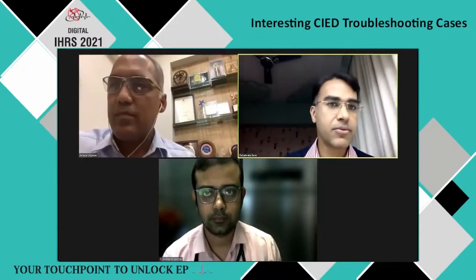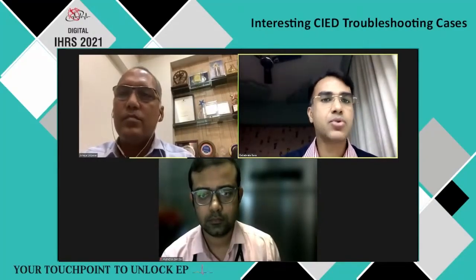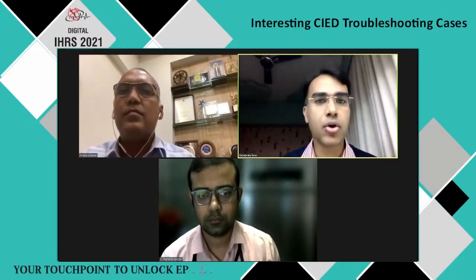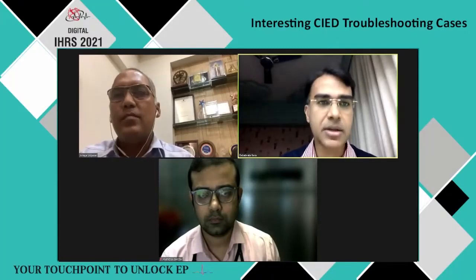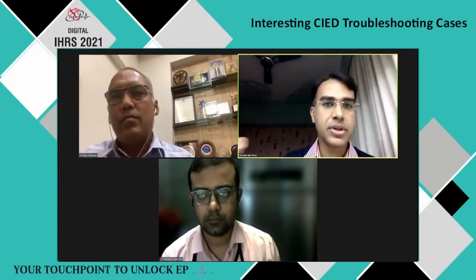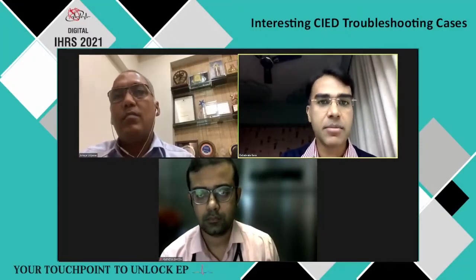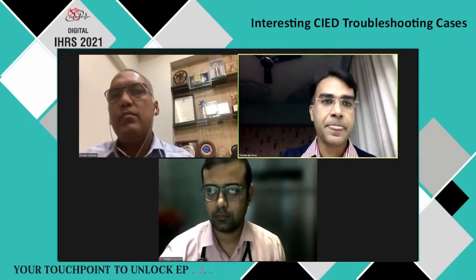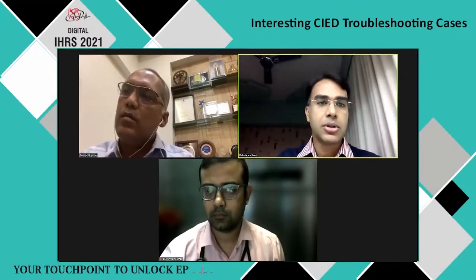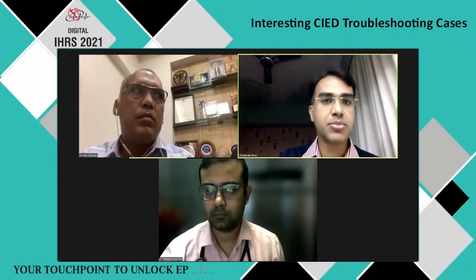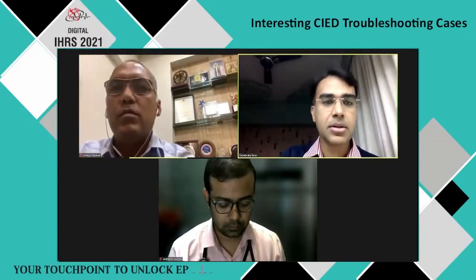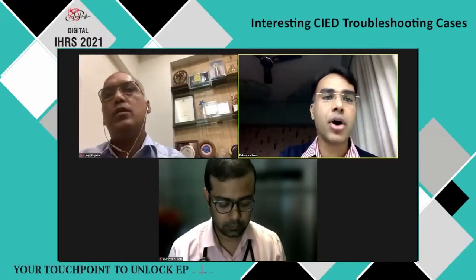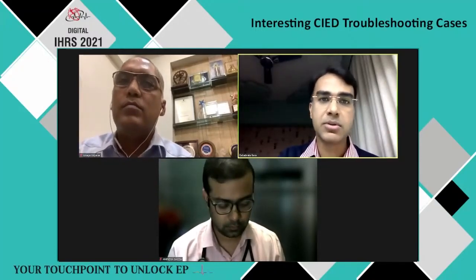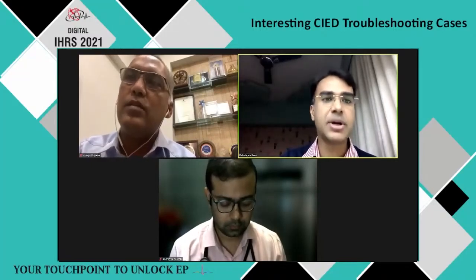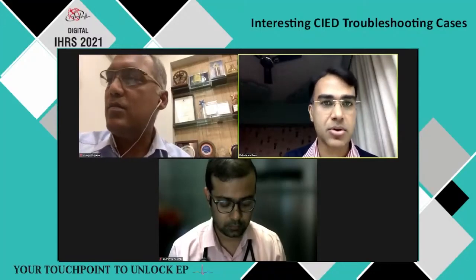The interesting thing which I found is that, let's say I programmed this patient's auto capture on 2 years back. And then generally we do not test the auto capture evoked response ratio at follow-up. What I found is that even the literature says that at least once every year, you should check whether this ratio, which was earlier favorable, is still favorable. So we should test that. Secondly, although this led to a little confusion, the patient was asymptomatic. Even the big literature says there is no reported catastrophe for this, because on follow-up they found that evoked response was always underestimated, never overestimated for some reason. That's why we are safe, but it will lead to battery drain because it will keep on checking the auto capture threshold.